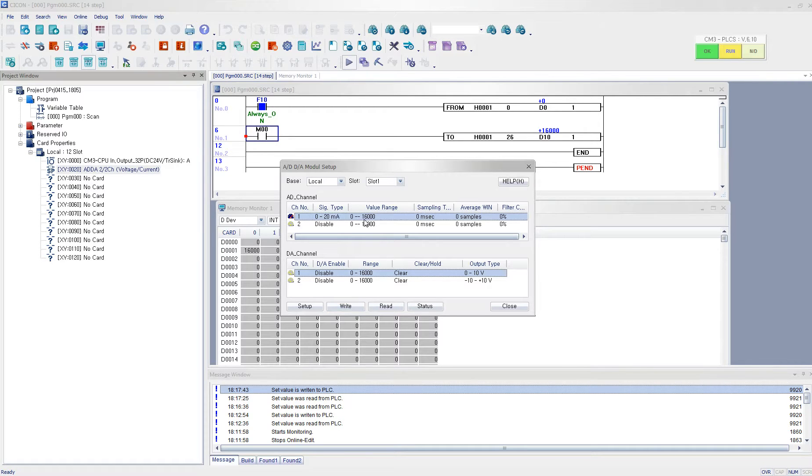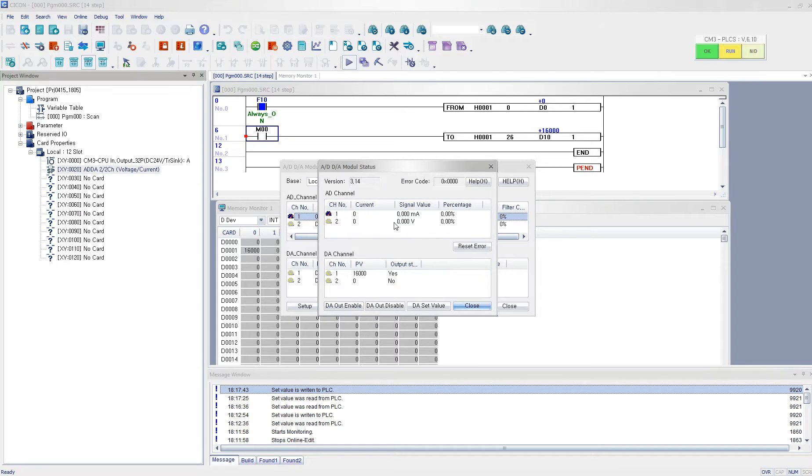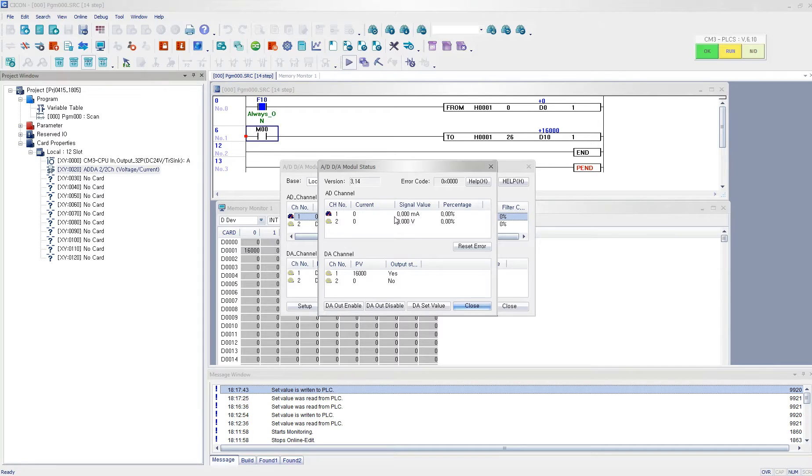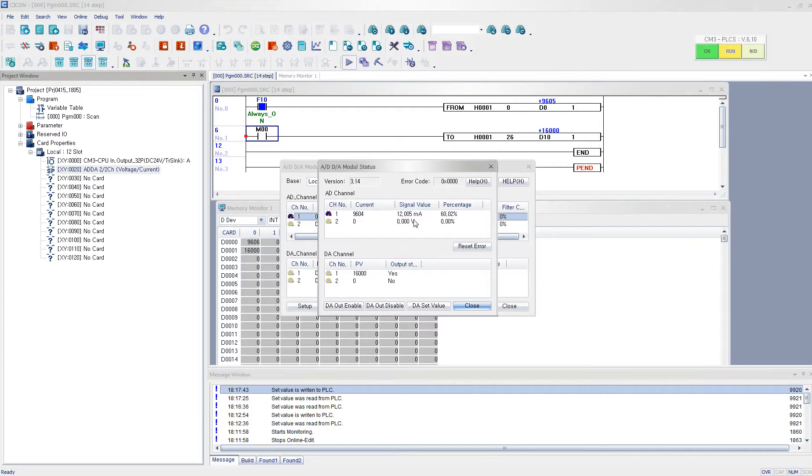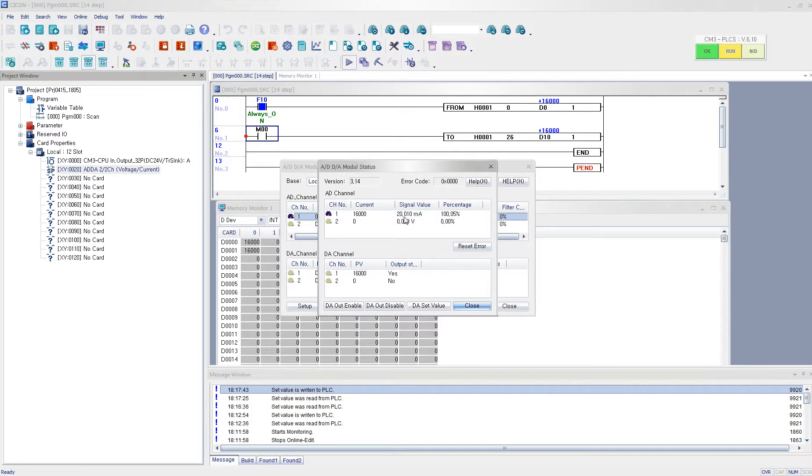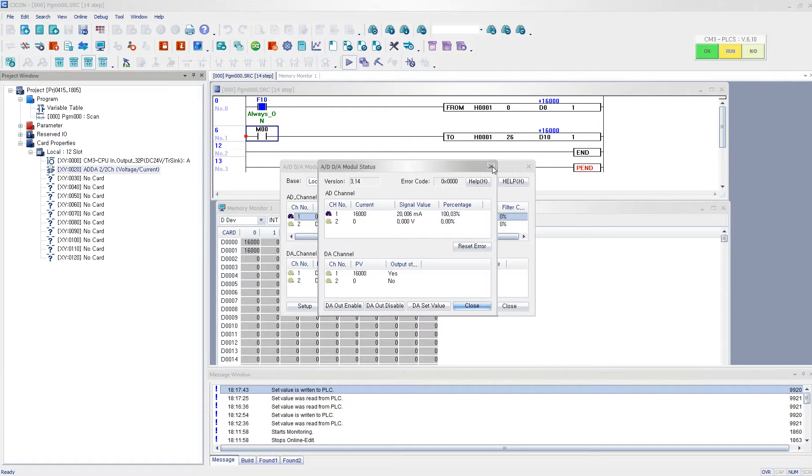So right now, it is reading 0 mA. But if I say I put 3 mA, then it should read 3 mA. Yes, it is reading 3 mA. And I enter 12 mA and it is reading 12 mA. And if I put 20 mA, then it is reading 20 mA. And the digital conversion value is 16,000, according to our configuration.